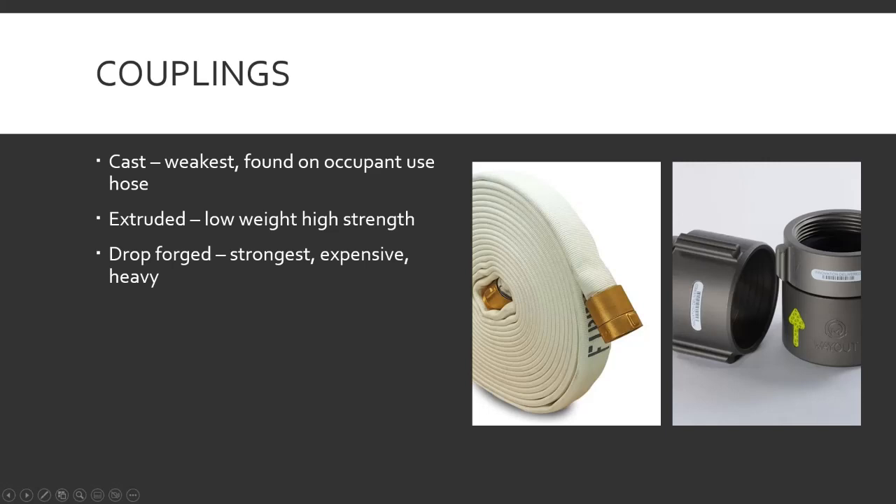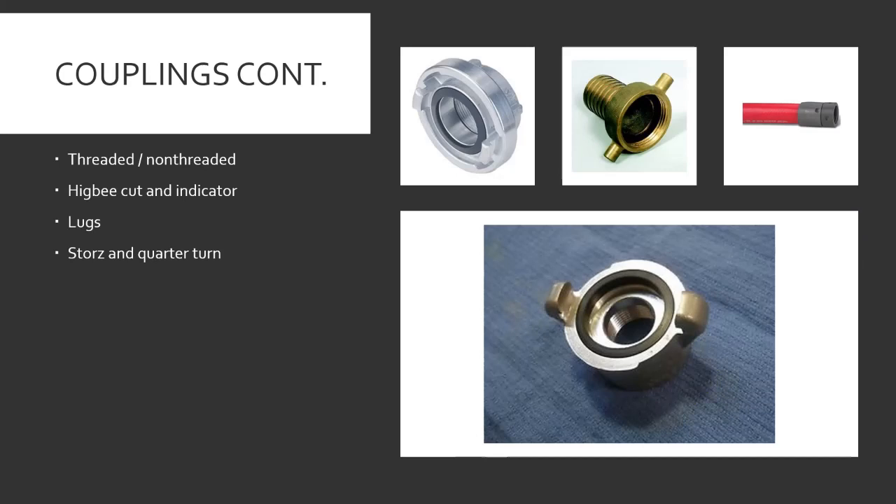The Higbee indicator is a notch on the lug that's in line with the cut. The swivel end that threads onto the other end of the hose will also have one, so you can look at them, line those two marks up, and connect your hose — it's all lined up on the inside. Lugs are the part you put the wrench to in order to twist, connect, tighten, or loosen hoses.